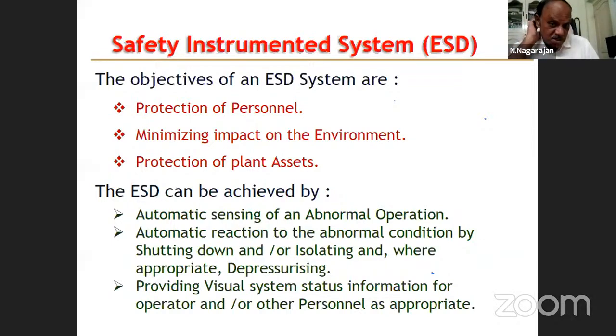How is ESD achieved? Automatic sensing of an abnormal operation. That is, let us say, gas leakage or liquid leakage, or there is some fire, you get some smoke or flame. There are detectors located at the important points where you feel there will be leakage, or all equipments will have these sensors. Smoke detectors, fire detectors. Okay. Even in the buildings, it is mandatory now. You must have seen in the buildings flame sensors, smoke sensors, etc. They will operate the deluge system. So water will be sprayed wherever there is a fire.